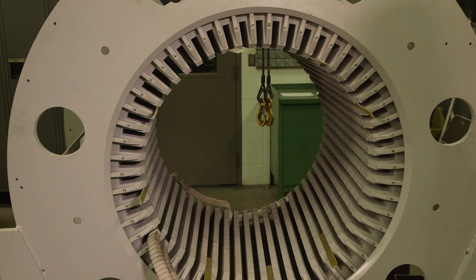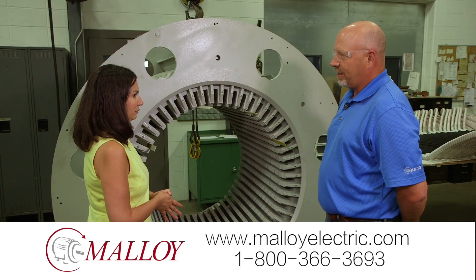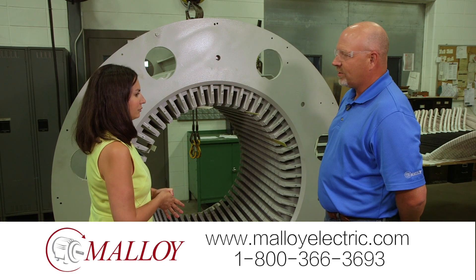At that point in time, we'll get ready and start inserting the coils into the motor. Once they get them fully inserted and installed, we'll do another series of tests, and then we'll release them to be connected. Once it's connected, we'll do another series of tests, and then we'll go through oven and resin cycles.